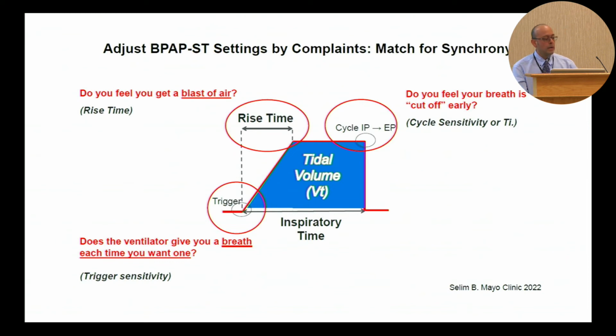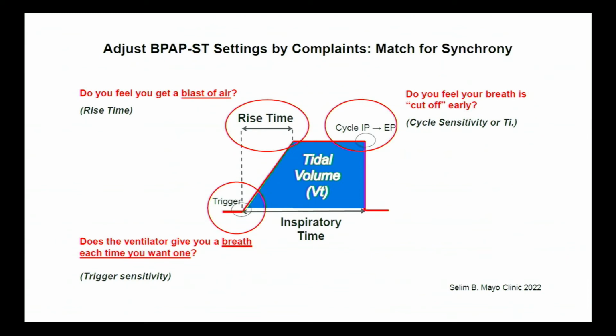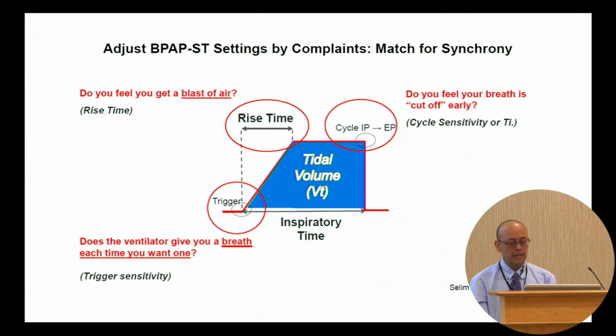These are things that you might hear from your patients mostly in the clinic. Do you feel that the ventilator basically follows you, that you are trying to trigger or you're trying to take a breath and you can't? Then you can adjust the trigger. The rise time is, as we discussed, how fast you're going to get there. So if the ventilator gives you a blast of air, then maybe you need to reduce your rise time. Is your breathing cut off earlier? Then you need to adjust your cycle sensitivity if you're doing it by flow, or your inspiratory time if you're cycling by time.